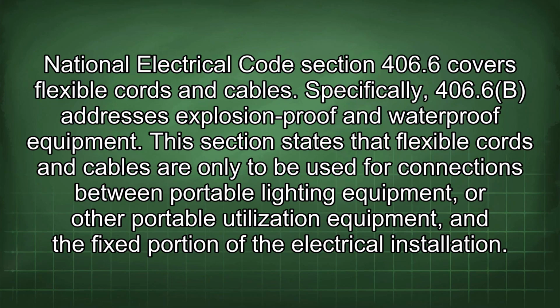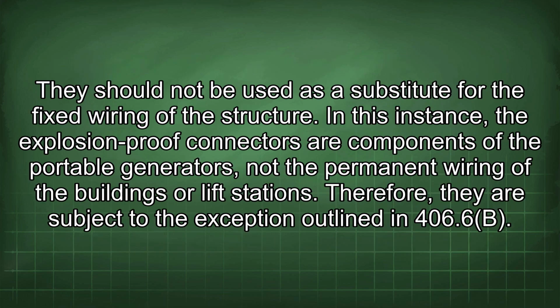National Electrical Code Section 406.6 covers flexible cords and cables. Specifically, 406.6b addresses explosion-proof and waterproof equipment. This section states that flexible cords and cables are only to be used for connections between portable lighting equipment or other portable utilization equipment and the fixed portion of the electrical installation. They should not be used as a substitute for the fixed wiring of the structure.